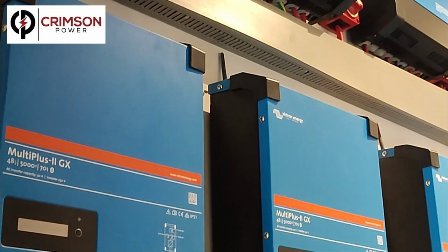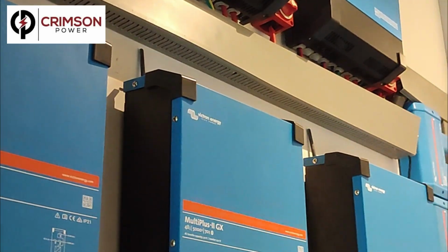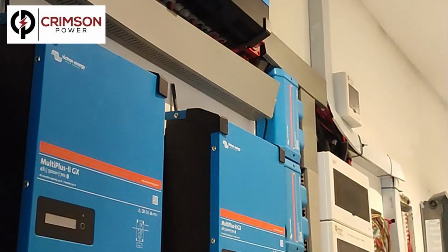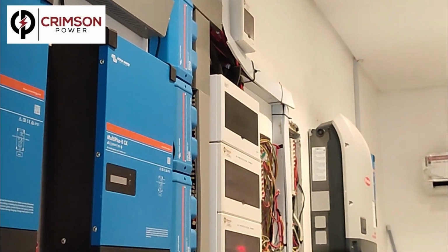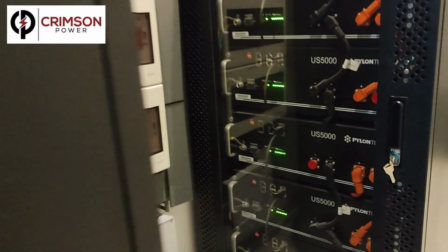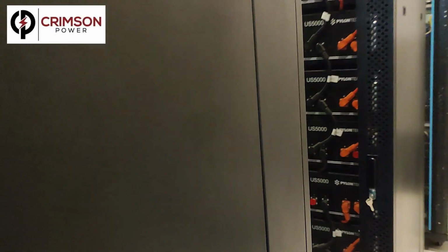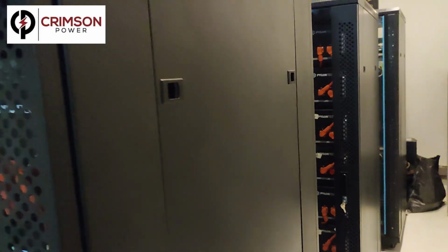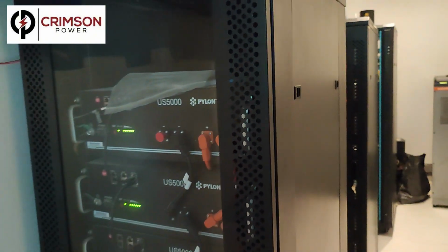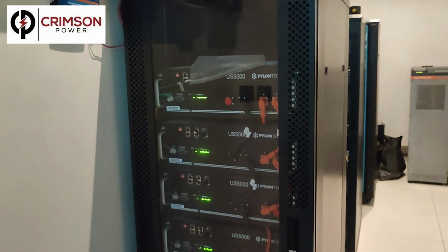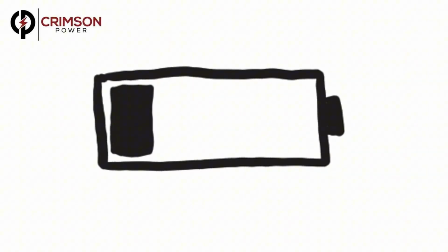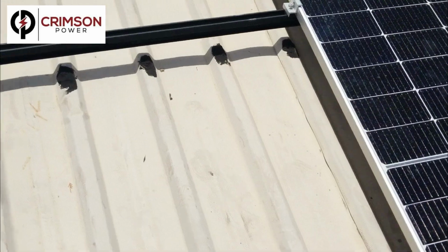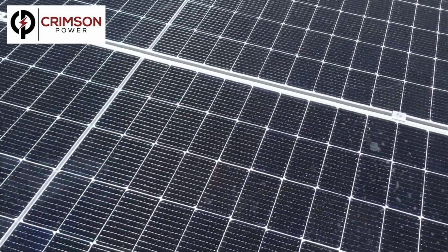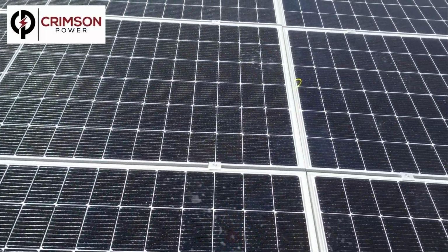And with the most recent upgrade now active, we expect the solar to consistently cover upwards of 75% of the home's consumption moving forward. The batteries, if you recall, 15 units of Pylontech US 5000, have been cycling daily, with an average state of charge between 40 and 90%. We're seeing healthy depth of discharge, usually down to about 30%, and a full recharge during sunlight hours. This Ikoyi home runs primarily on sunlight, and the numbers speak for themselves.